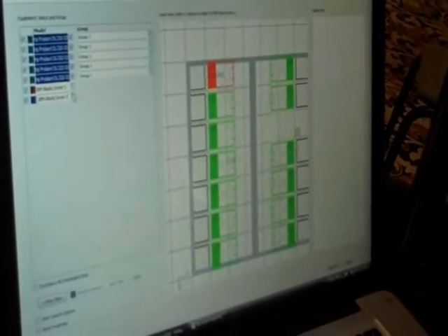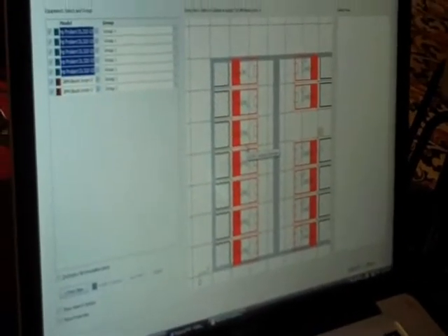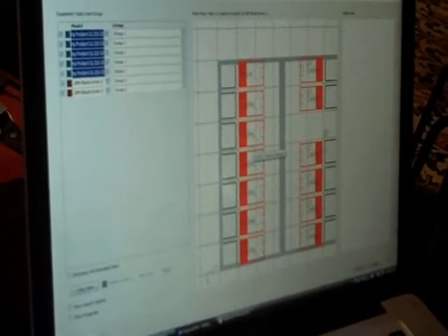I also want to install these two Blade Center E's. Right away I see that if I install in this cabinet, it will violate cooling. Let's say I wanted them together for whatever purposes — now everything is violated because of cooling limits. At this point, operations is stalled. They can either proceed while ignoring the consequences, or they can get engineering to come in and do analysis and help them out. I'm going to install without paying attention to cooling into this cabinet, C5. Install in cabinet and it shows up there as a reservation. Submitting my change request and hitting finish.